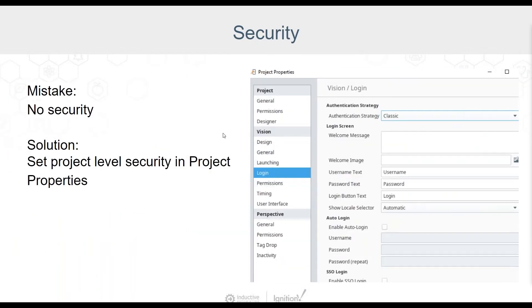Now let's switch over to project-level security. For some projects such as status displays, an auto-login in Vision or allowing no login for Perspective is appropriate. Consider requiring a login for any projects with sensitive information or set point control. For Vision projects, you can set an identity provider or user source and required roles on the project general tab, designer permission on the project permissions tab, auto-login on the Vision login tab, and additional permissions on the Vision permissions tab. For Perspective projects, use the Perspective permissions tab and select security level zones for login.